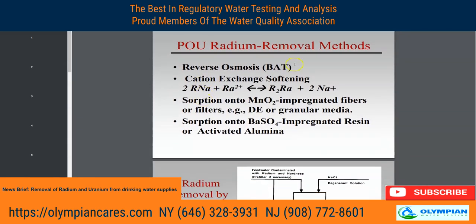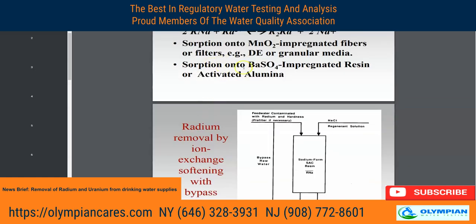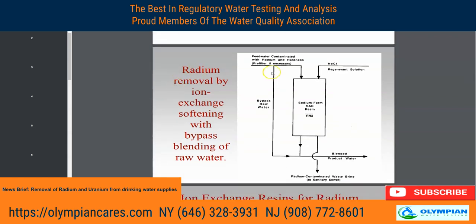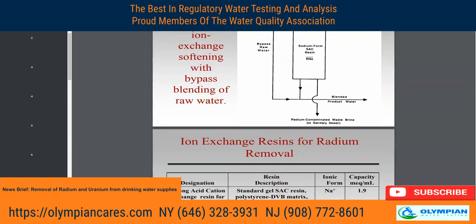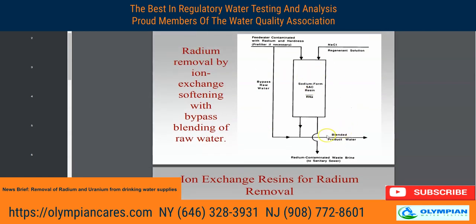And you can also see the removal methods for radium: reverse osmosis, cation exchange softening, sorption onto MnO2 impregnated fibers or filters or granular media, and sorption onto BaSO4 impregnated resin or activated alumina. And we can see the diagram here for radium removal by ion exchange softening with a bypass of blending raw water. You can see the blended product water, the bypass raw filter, the feed water contaminated with radium hardness, pre-filter if necessary, sodium-form resin, and the regenerate solution.